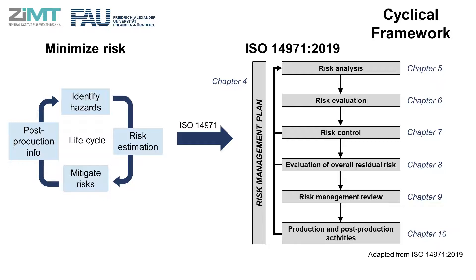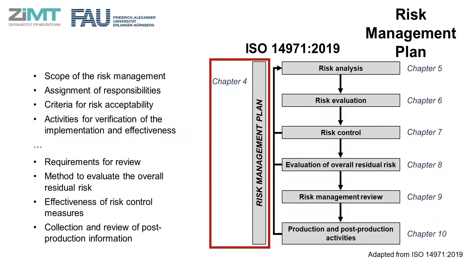Now that we are familiar with the background of risk management, we can dive deeper into each part of the process. When applying the standard, the first thing you will need to do is establish and document a risk management plan. The risk management plan defines the scope of the risk management process, including but not limited to the responsibilities, criteria for risk acceptability, and activities for verification. As the schematic shows, this plan accompanies all the subsequent processes, and therefore its quality is crucial for the overall risk management.